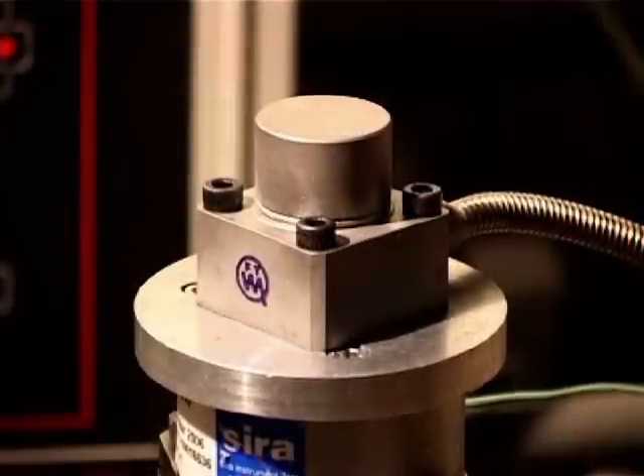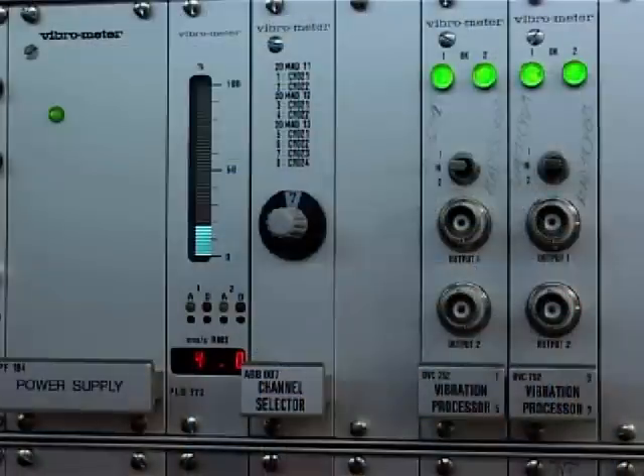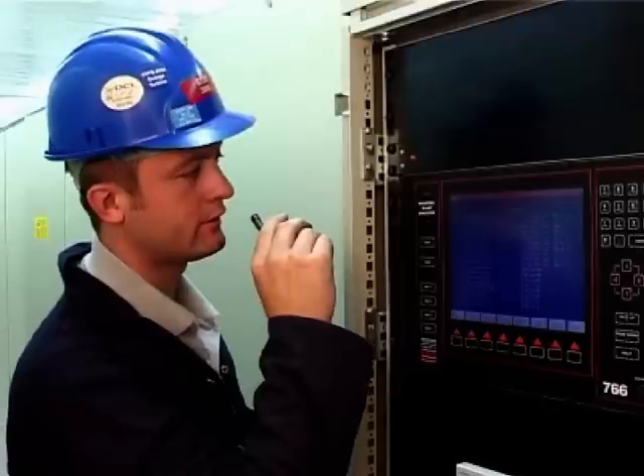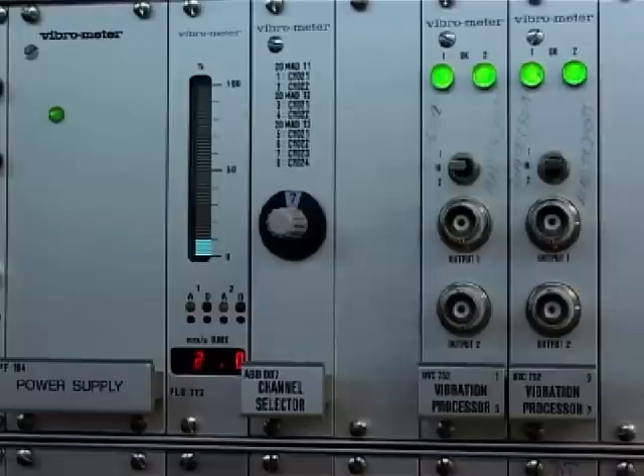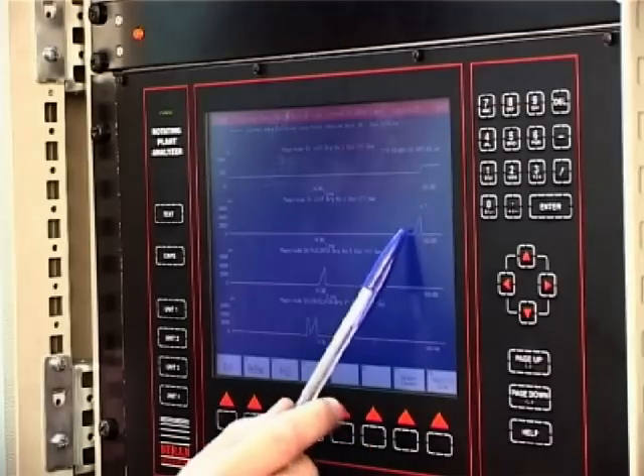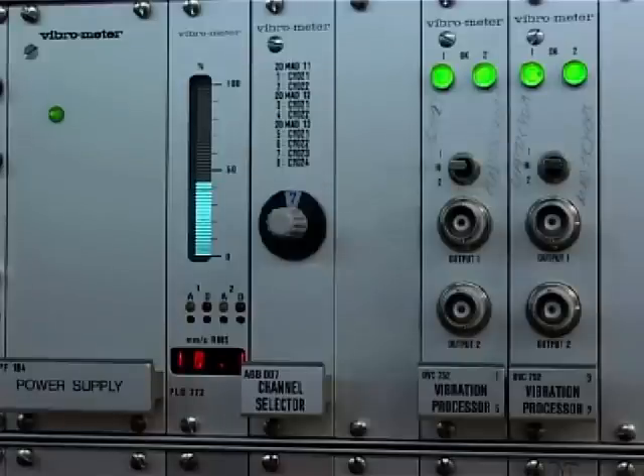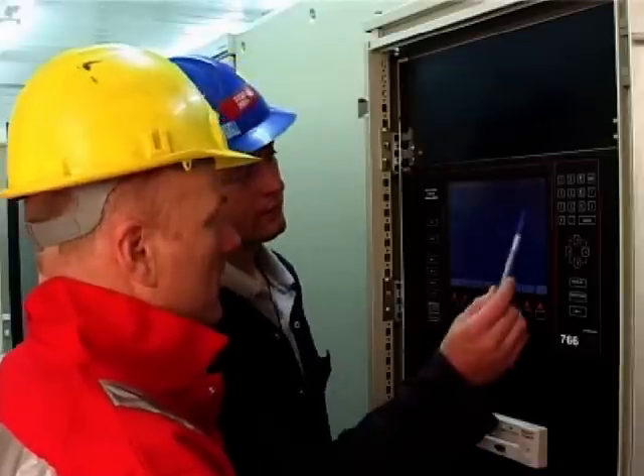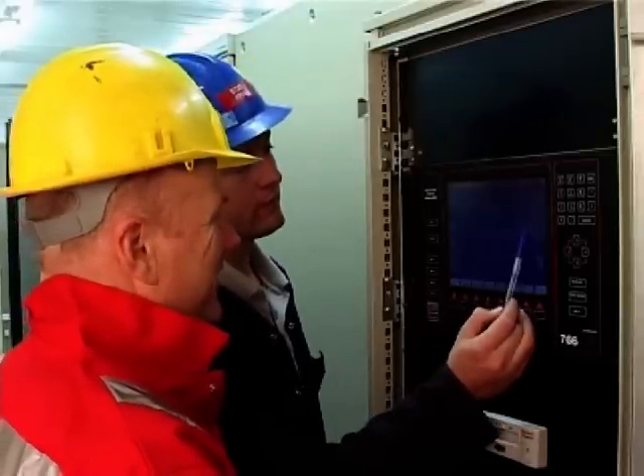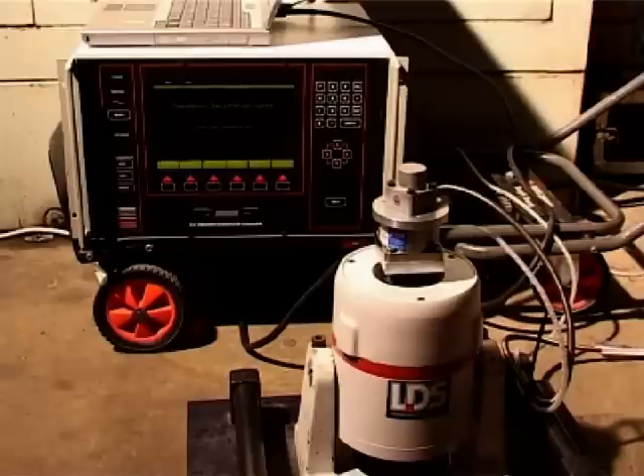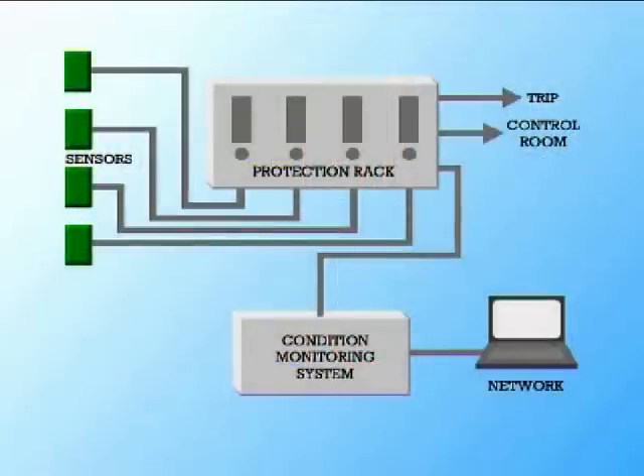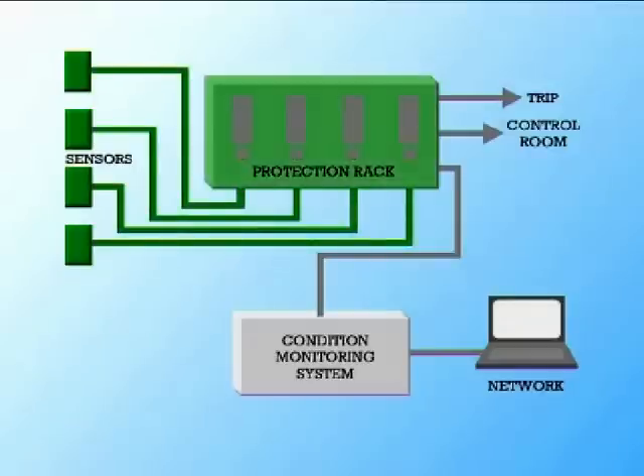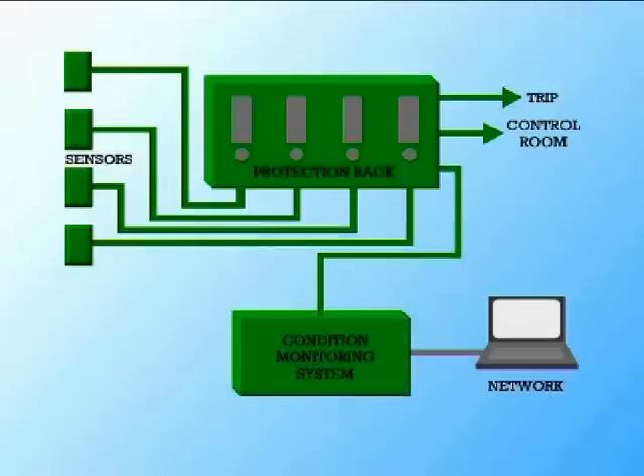The test typically comprises a number of step increases in vibration, and whilst running, a second technician monitors the readouts on the condition monitoring and plant protection systems to ensure that they're reading an identical vibration level to that being generated by the TransCal system. After the calibration test has been completed, the engineer may also check any chart recorders and other control room recording systems to ensure correlation with the same vibration step levels that were provided by the TransCal system. In this way, the complete vibration measuring chain has been calibrated. This ensures that accurate machine condition is established from verified sensors and instrumentation at a range of vibration levels and frequencies.